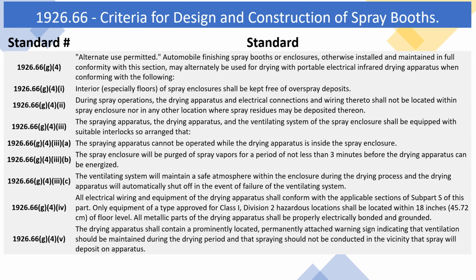1926.66 G4 Alternate use permitted. Automobile finishing spray booths or enclosures, otherwise installed and maintained in full conformity with this section, may alternately be used for drying with portable electrical infrared drying apparatus when conforming with the following. G4-1 Interior, especially floors, of spray enclosures shall be kept free of overspray deposits. G4-2 During spray operations, the drying apparatus and electrical connections and wiring thereto shall not be located within the spray enclosure nor in any other location where spray residues may be deposited thereon.